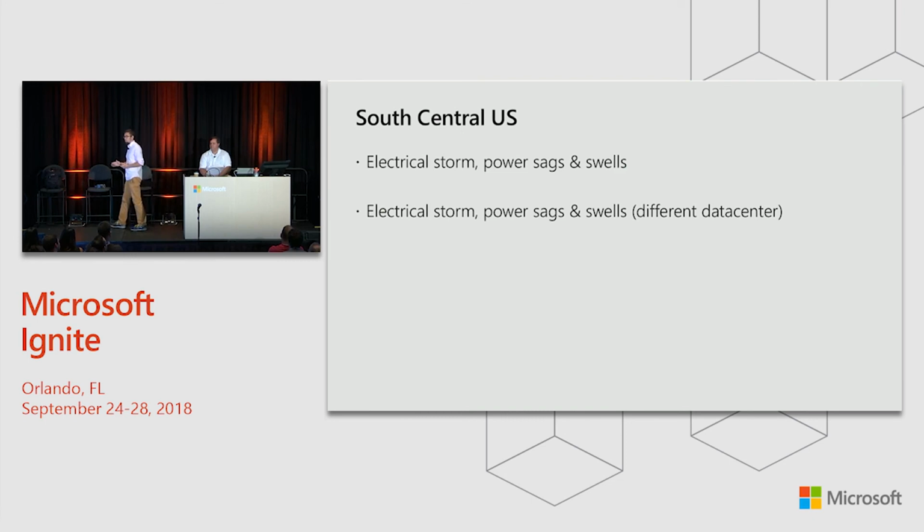and they didn't triage accurately. The RCA for this incident is still being finalized and will be published, hopefully, in the next couple of days. But what we've learned is that the engineers on there didn't triage the alerts correctly, and as a result, they missed responding to the chiller plant, and they were looking at other events within the data center. Critical events, but not as critical as a chiller plant. We understand that was a very painful thing for us to learn, but as I said, we want to build the transparency and the trust, and we wanted to share it.